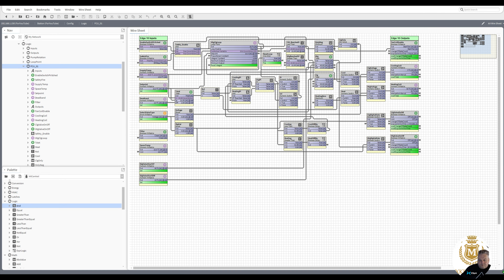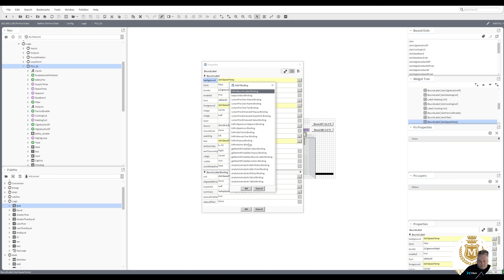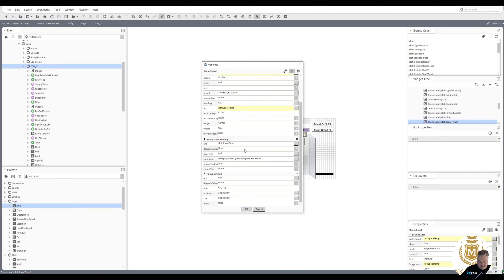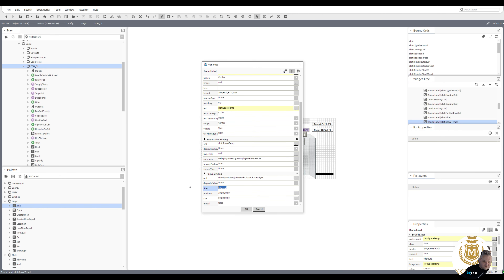Welcome back to the N4 Learning Channel. We're still on the Edge 10 and in the last video I put some histories on. What I want to do is where the graphics are - as you put your mouse over you don't see anything highlighted. So let's add a history to that point. I'm going to do a pop-up binding and just take that history, paste it into the ORD, and go to chart for default view. I'm going to change the pop-up to space temperature history.